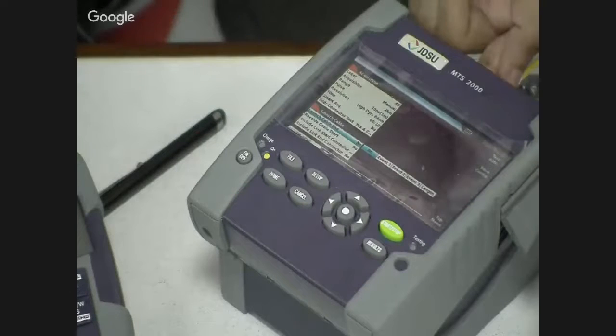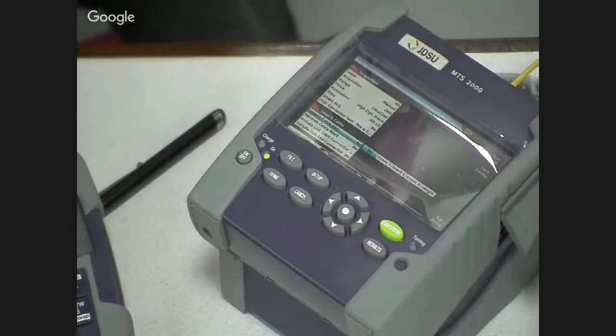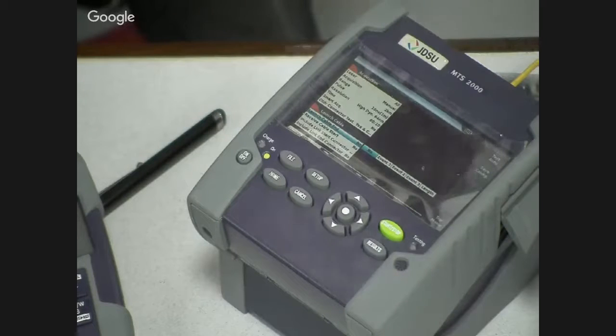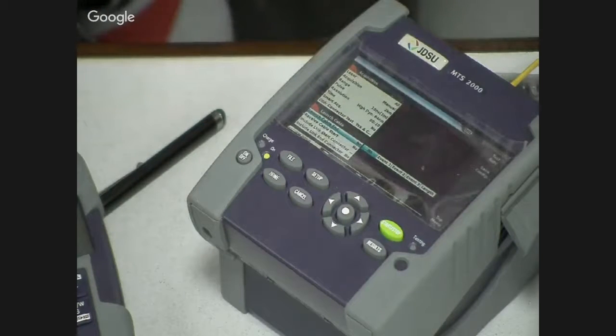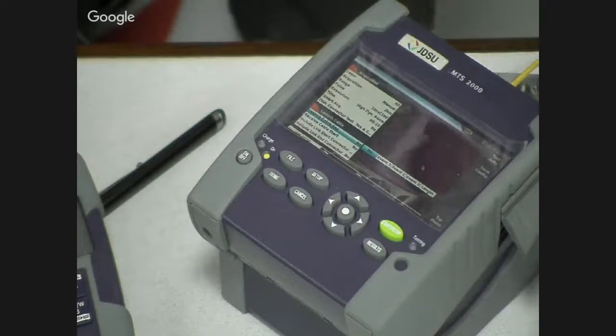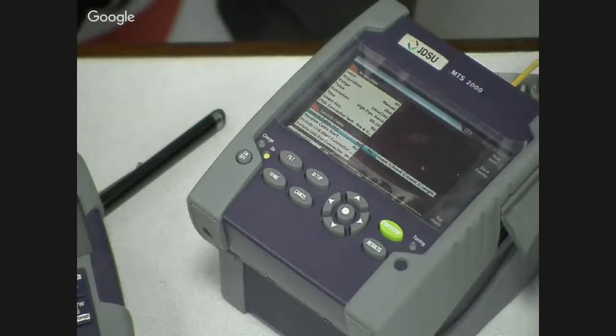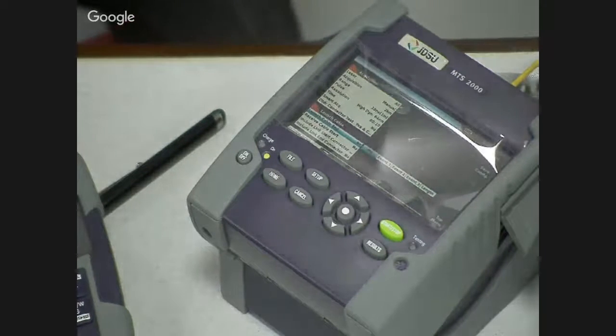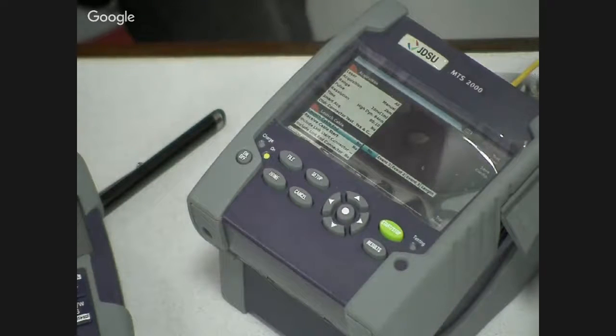What you do is connect on the OTDR side. The second side is where we use a mechanical splice, so that the fibers are just aligned together with that glue. You don't do a fusion splice at that time because you just need to test. One side is already connected, the second side, the fiber side, you just insert and test. So the fiber is tested. What is the loss in that fiber? What is the distance of that fiber? That is tested.